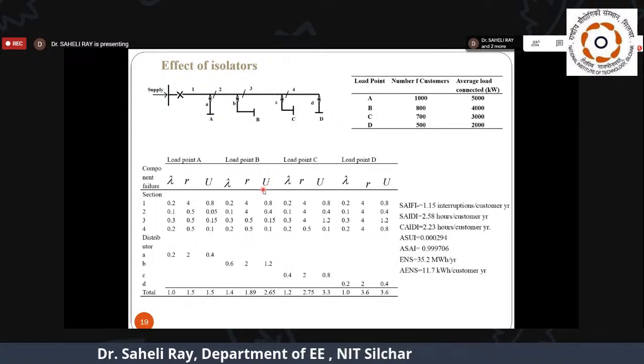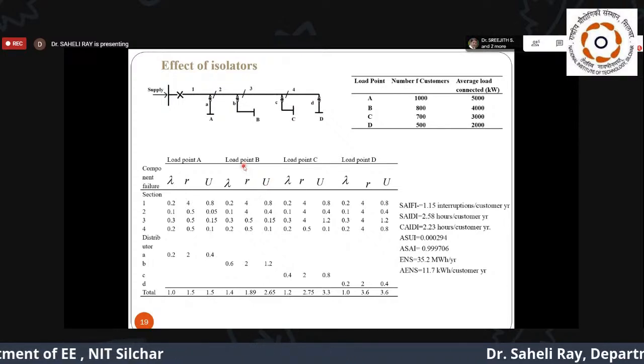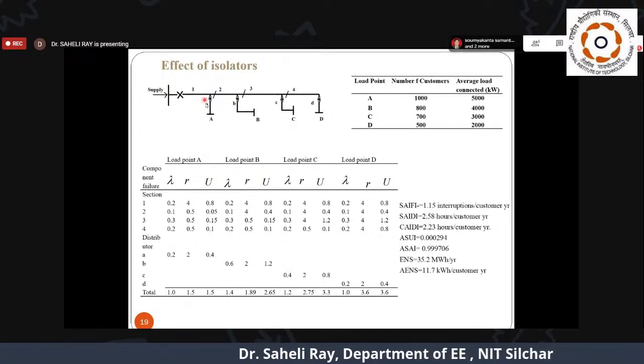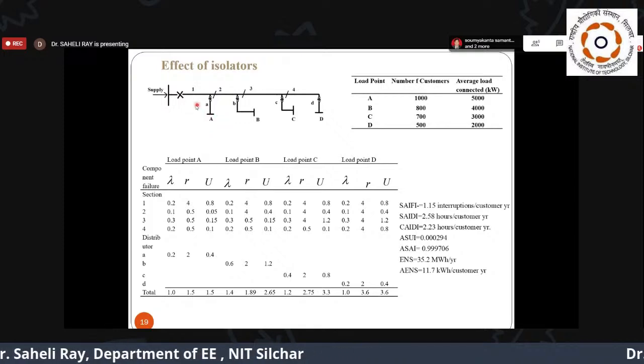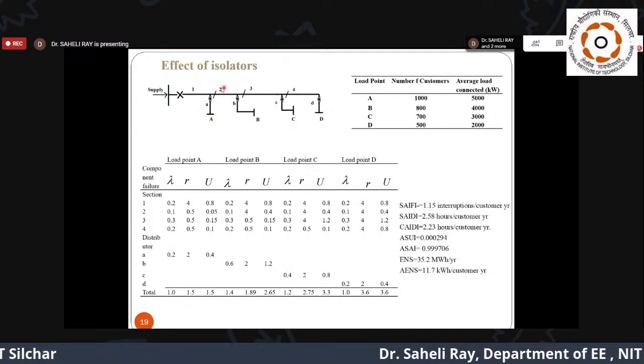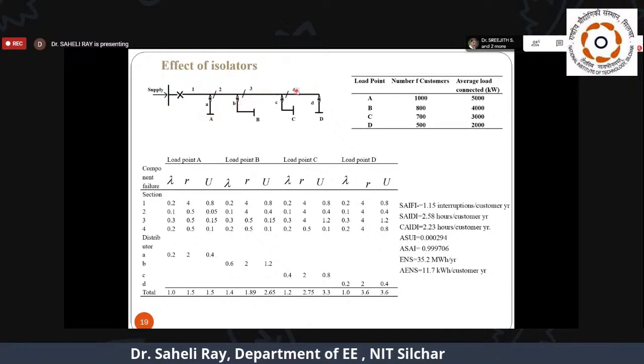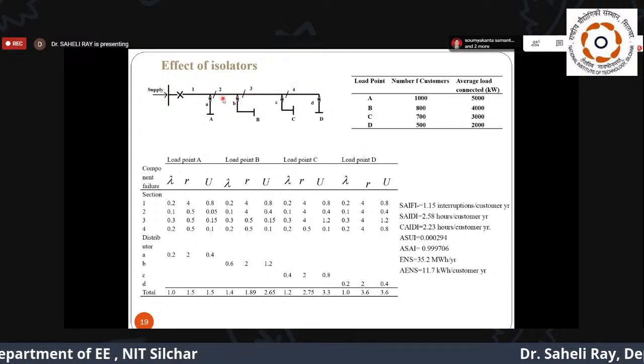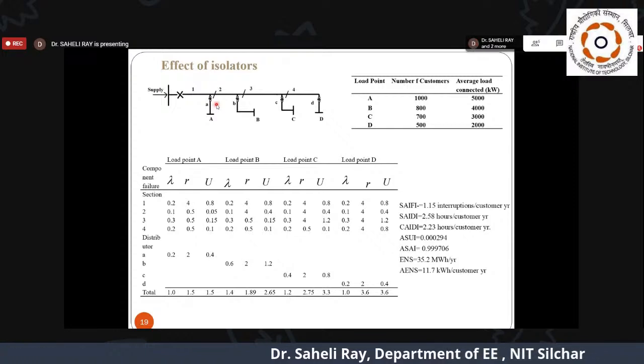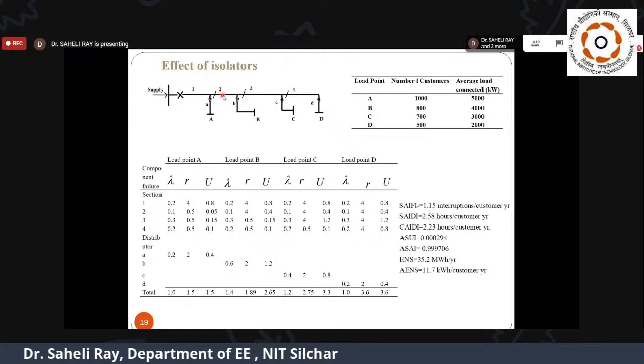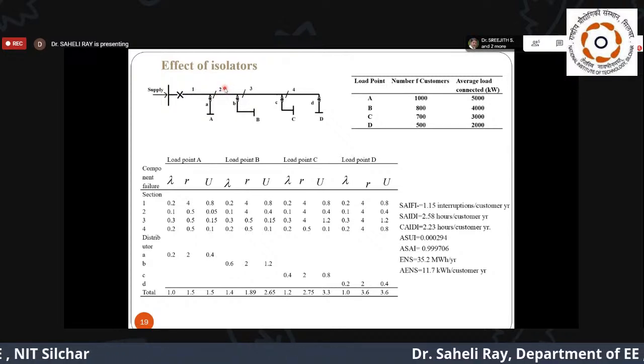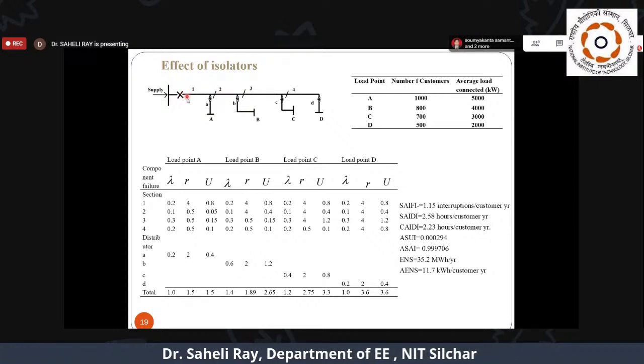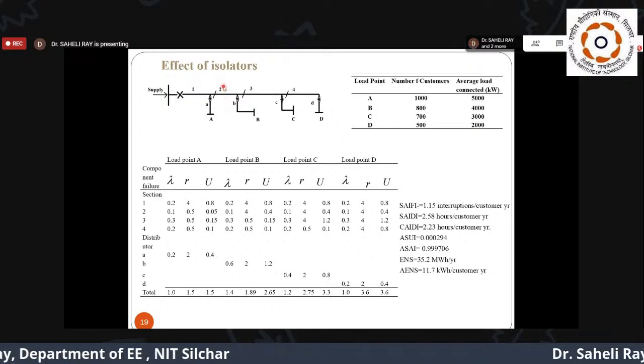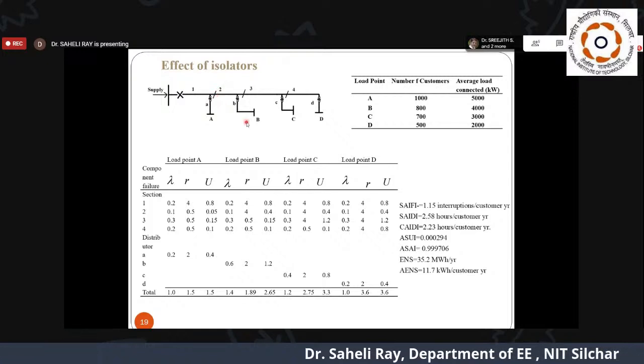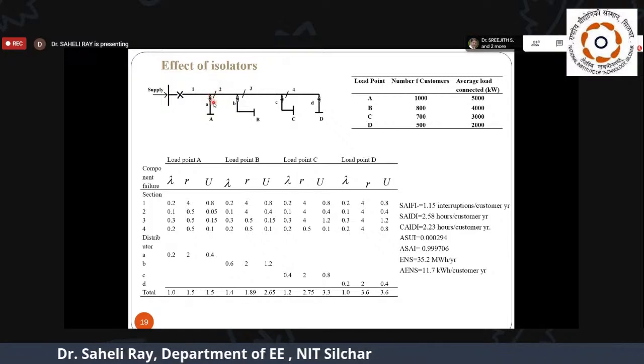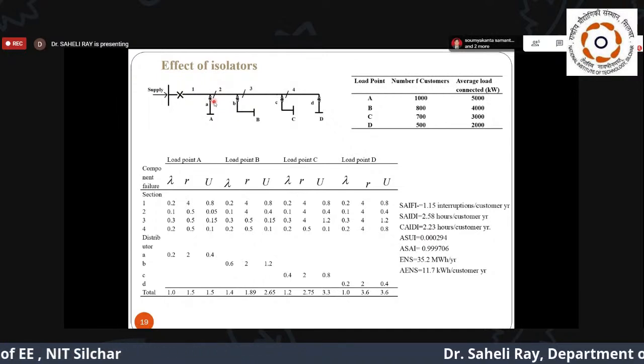Now, again, let us see what is the change in the indices of the load points. For load point A, let's say fault occurs in 1, load point A will be affected. Even if fault occurs in 2, load point A will be affected. In 3 also it will be affected, 4 also it will be affected, no doubt. The failure will be there. See, isolators cannot isolate instantly in on-load condition. These switches cannot operate and break the healthy portion from the faulty portion. But what they can do is, once the circuit breaker operates when a fault occurs, then these switches can be operated to cut off the healthy portion from the faulty portion, and power may be resumed to the healthy portion much before the fault is repaired, right?